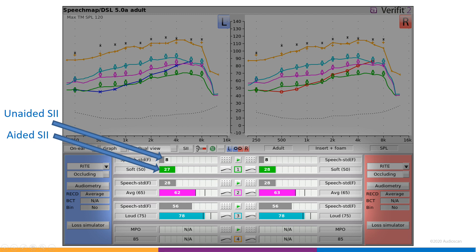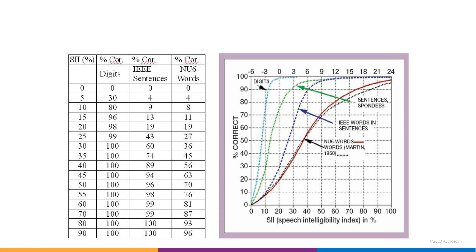SII can be a helpful tool, especially when counseling on the potential benefit of amplification, as it can be used to predict performance on tests of speech understanding. When explaining these values to a client or family member, it's often useful to have a graph showing how they relate to predicted speech intelligibility. This graph, which is found in all AudioScan help menus, shows SII along the x-axis and several curves which show how SII can predict percent correct when using various types of speech materials.